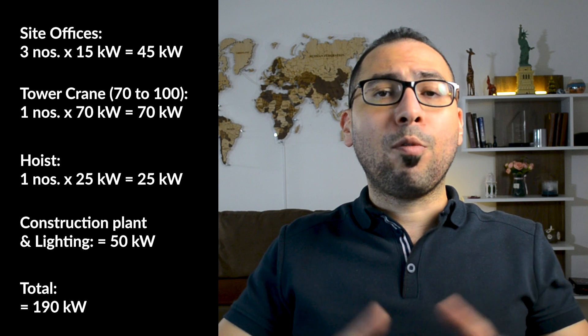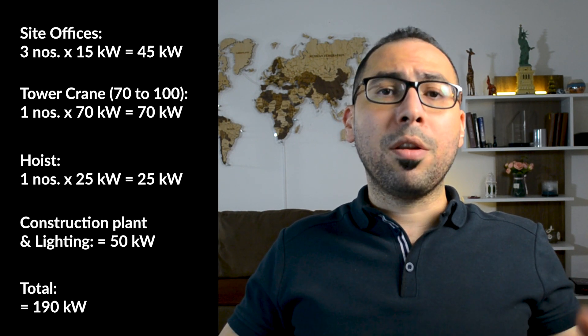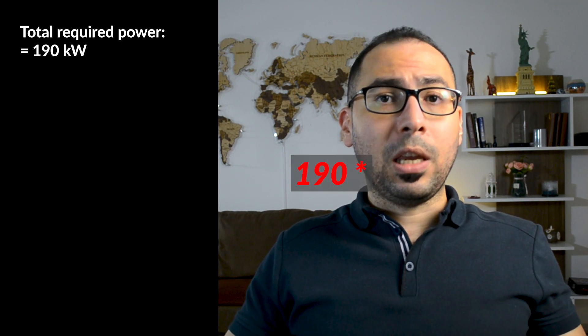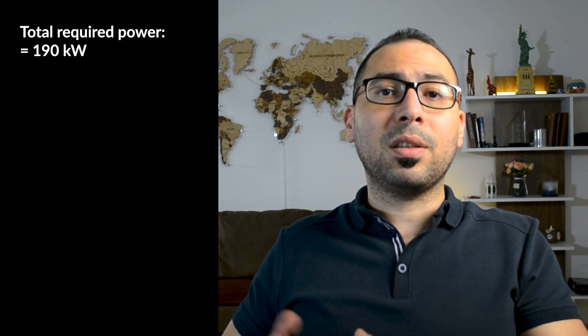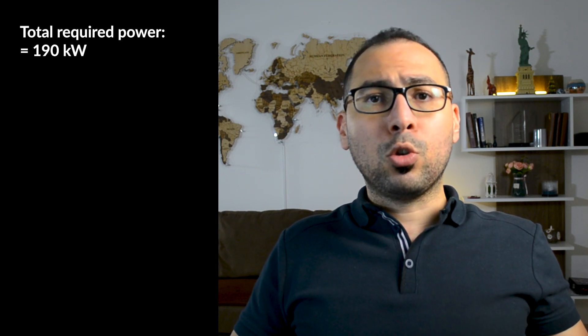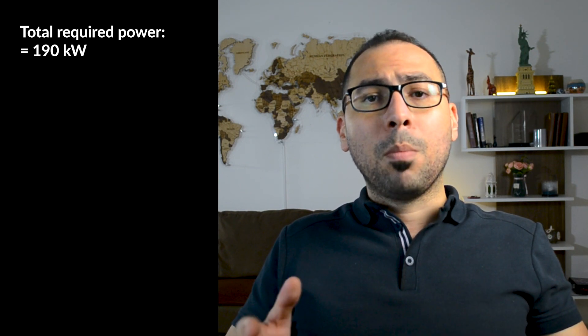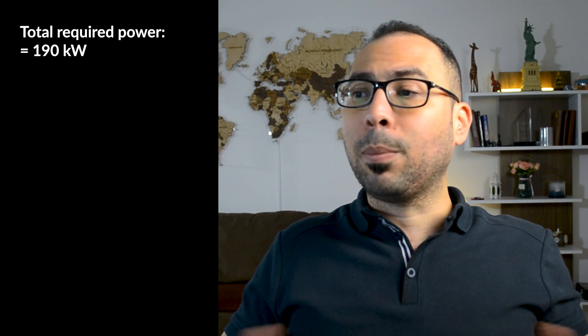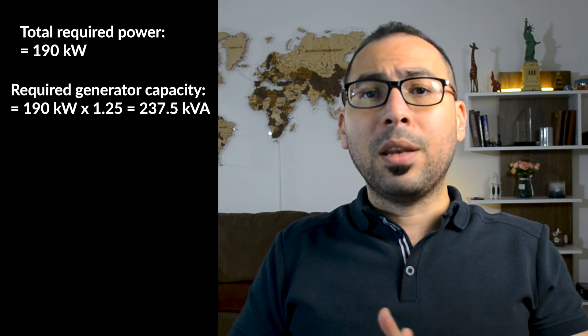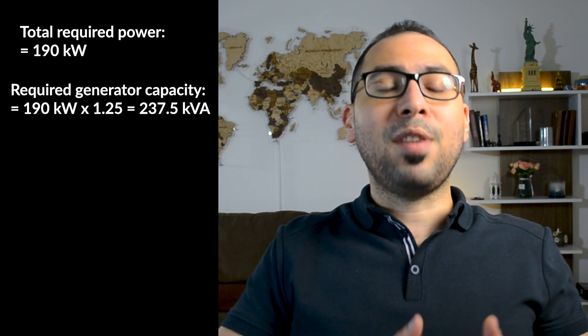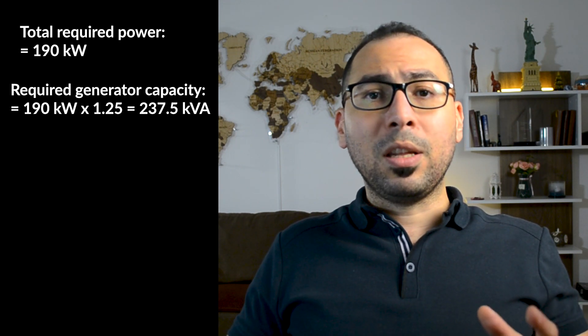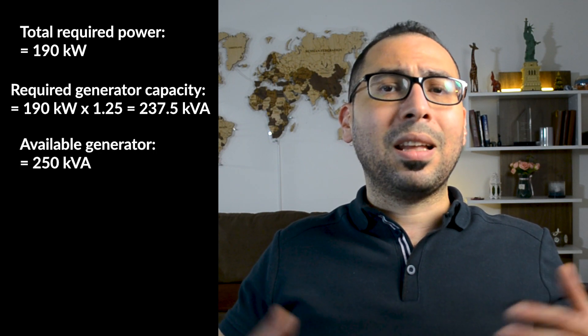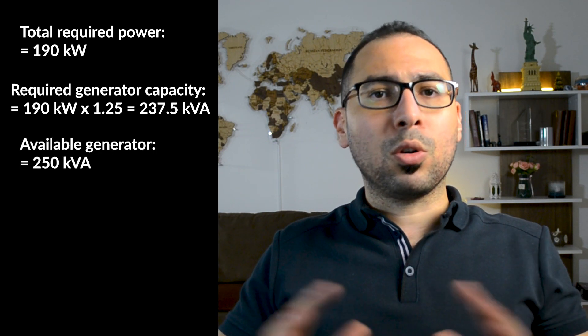I need an actual power of 190 kilowatts to run my project. To get that, I need a generator of a specific capacity — this is the apparent power. The apparent power is equal to the actual power multiplied by 1.25. So 190 kilowatts multiplied by 1.25 gives 237.5 kVA. KVA is the unit for apparent power and for generators.